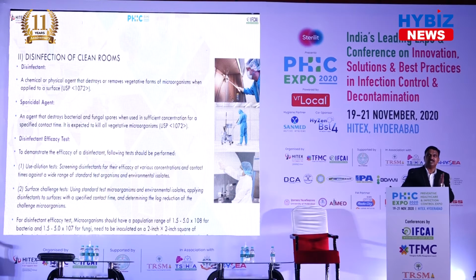In the use dilution method, the required disinfectants at specific concentrations are challenged with microorganisms, and the efficacy is determined. The concentration which is more effective will be used for the surface challenge test on surfaces actually present in the clean rooms.